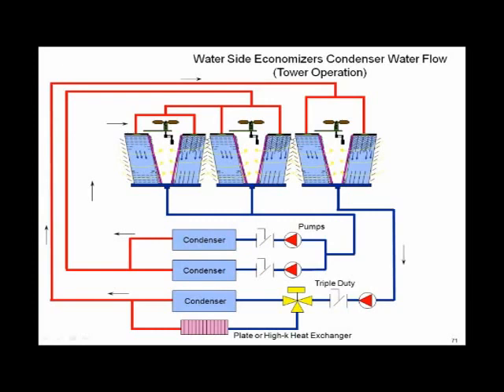I've got 2 sets of pipes. I got 1 set of pipe for the waterside economizer and a dedicated machine. I got another set of pipes for my regular centrifugal reciprocating machines, whatever they may be, for head pressure control. In other words, I've got a dedicated cell to the waterside economizer. In other words, I might have to run 2 pipes, 2 pieces of pipes. And you haven't been doing that.